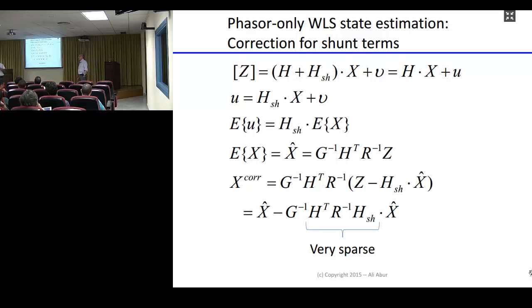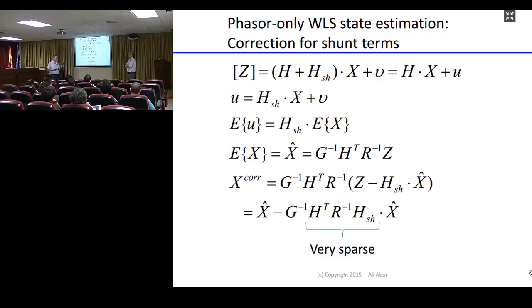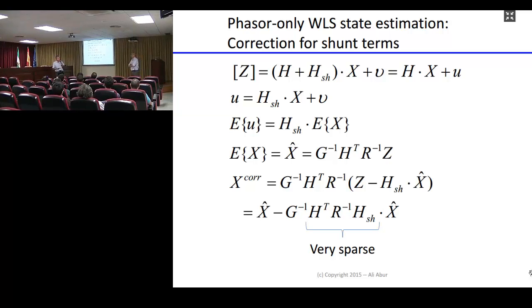Yes, last week we had an engineer from Endesa here giving a seminar about the control centers and all the infrastructure they have for control and monitoring, including state estimation. I asked him the same question, whether they are concerned about cyber attacks. He told us that so far at the high voltage levels, they use a private network, not connected to the internet, not IP. So in those cases, there's no possibility for a hacker to get into the data and modify it arbitrarily. But they are really concerned about the distribution system, because they are increasingly using public systems, like GPRS. They contract internet service from utilities, so every low voltage secondary substation may have an IP address. So they are using the internet, and in this case they are really concerned because this is a possibility.